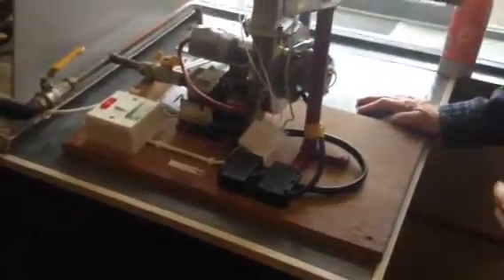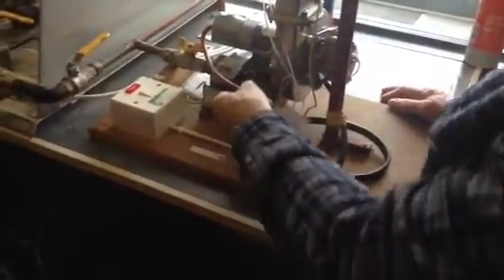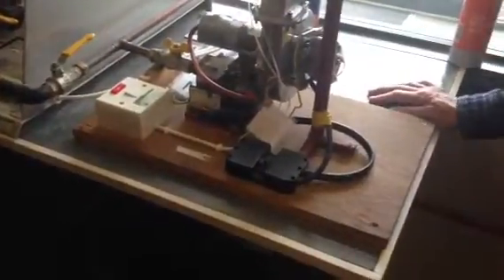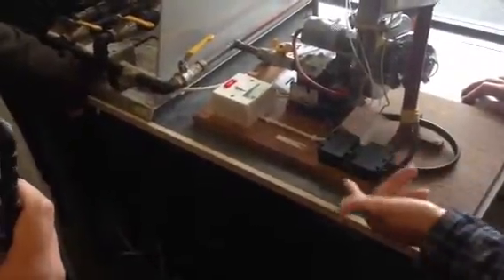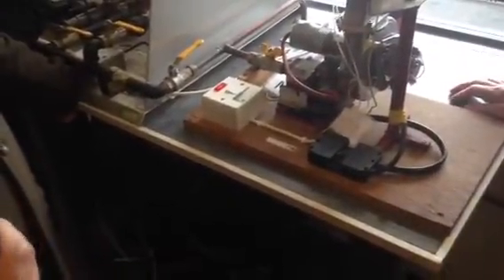Right, to test. You're going to have your gas on, and make sure your reset button down there is set. If it's off, you push your reset button so you want it going again. Sometimes it will switch itself off when you first switch it on. Other times it's left from the previous person that's been on the rig, you know what I mean? So it's an easy one to miss, isn't it? But sometimes if that tube's down here somewhere and you're still looking at that and thinking it won't go on, just make sure you press your reset.